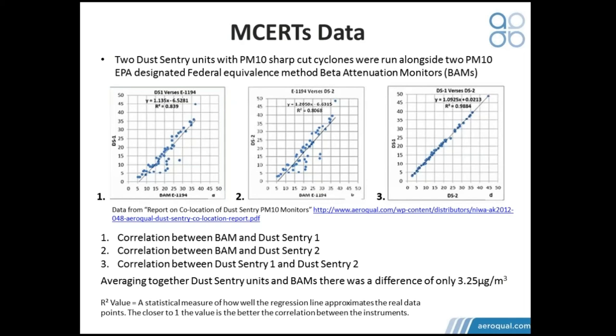You can see the correlation is very good. The average difference between the BAMs and the Dust Sentry units was only 3.25 micrograms per cubic meter, so a very high statistical correlation between the instruments. Incidentally, this test was done independently for the purposes of achieving MCERTs certification by the UK Environmental Agency.